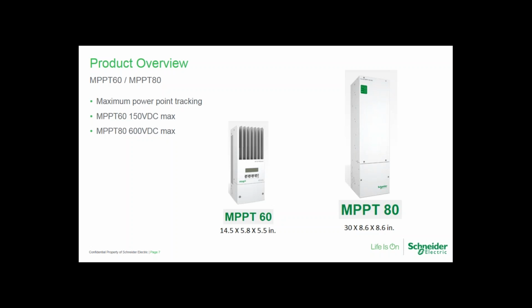The next question we have: how many devices can a single ComBox support? Great question. So typically your Xanbus network has a bandwidth of 20 units. The inverter chargers require 3 units, and all the other accessories, including the charge controllers, require a single unit of bandwidth. The largest system that I've personally experienced in a split phase configuration is 3 XW inverters and 8 MPPT 80 charge controllers. Then you start approaching the limits of what a single network can do.